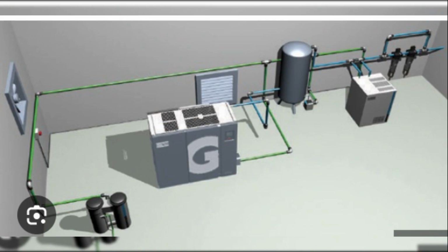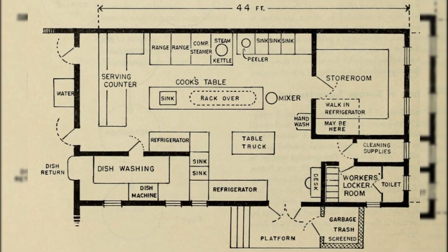If BMS exists, integrate room temp and humidity sensors. Kitchen storerooms must be kept between 50 and 70 degrees Fahrenheit using an electric heat pump system. The outdoor unit should be placed next to the walk-in condensing units, and if they're outdoors, they must be in a secure cage. If that's not possible, the outdoor heat pump unit must be in another secured location. For projects with a BMS or DDC system, the controls contractor must provide both temperature and humidity sensors, and integrate them directly into the network.